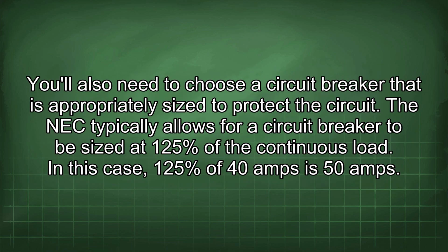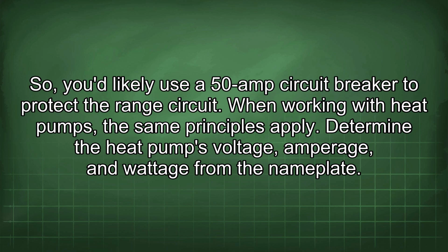You'll also need to choose a circuit breaker that is appropriately sized to protect the circuit. The NEC typically allows for a circuit breaker to be sized at 125% of the continuous load. In this case, 125% of 40 amps is 50 amps. So, you'd likely use a 50 amp circuit breaker to protect the range circuit.